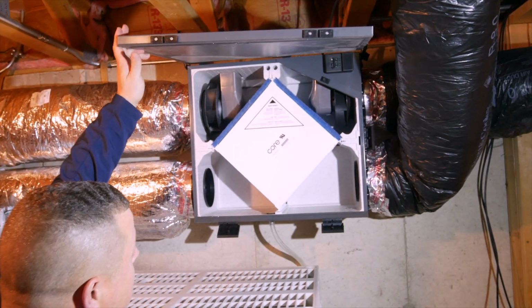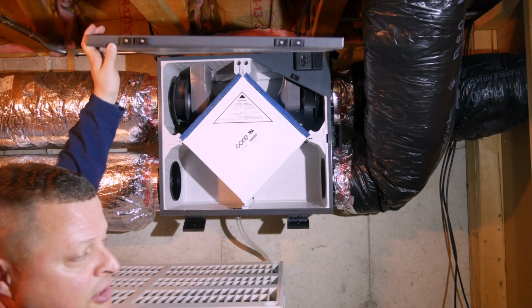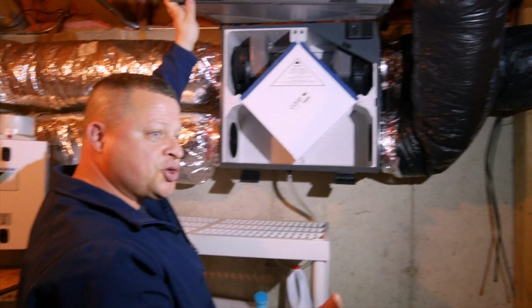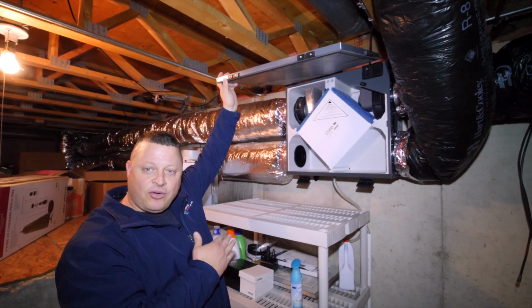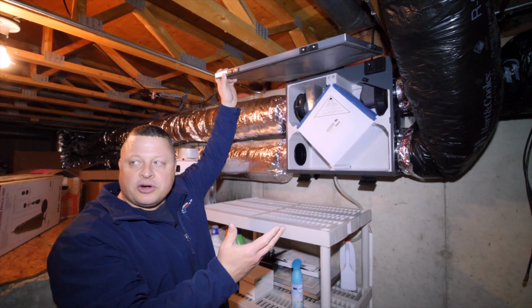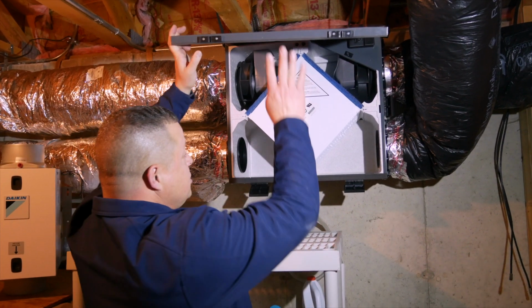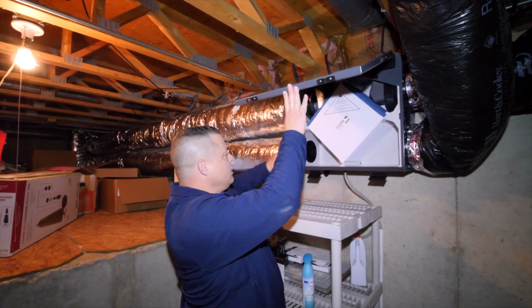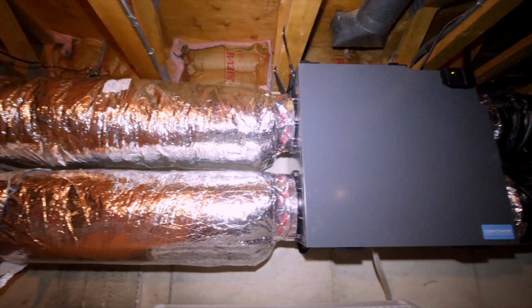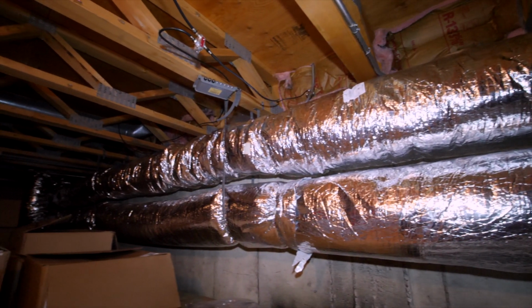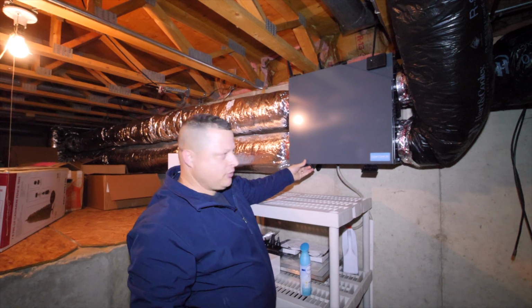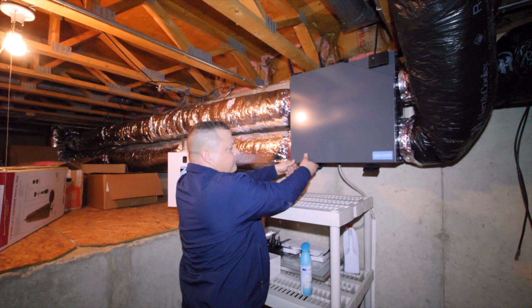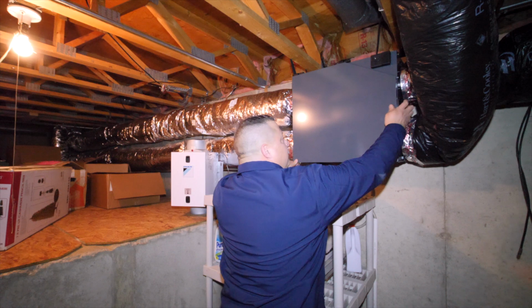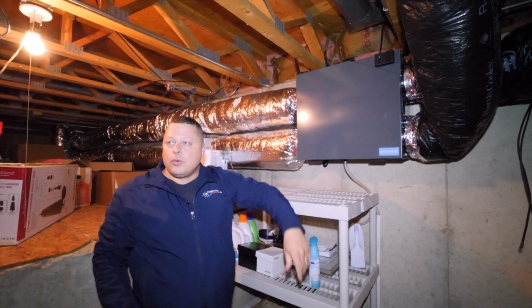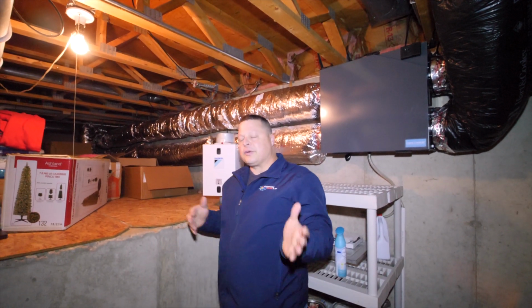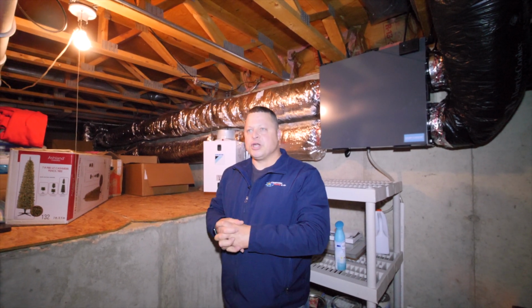Okay, so that's your main core, and you have a motor on each side. That's adjustable so that you have an equal amount of pressure drawing air from inside the house, and then you're drawing fresh air in from outside. This is your core where it exchanges, so you'll bring fresh air in, that goes in, and then you're forcing stale air out. Your ventilation in a home is listed as the most important when it comes to air quality. You're taking that old nasty air out, which is quite a bit more polluted than outside air. You're getting rid of that air and then bringing fresh air in.